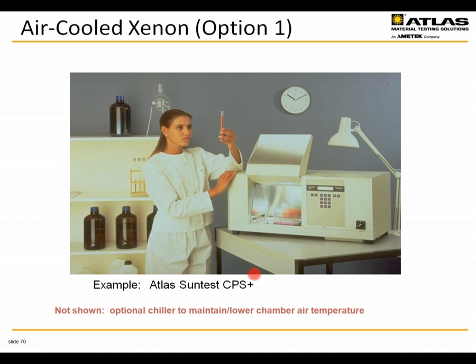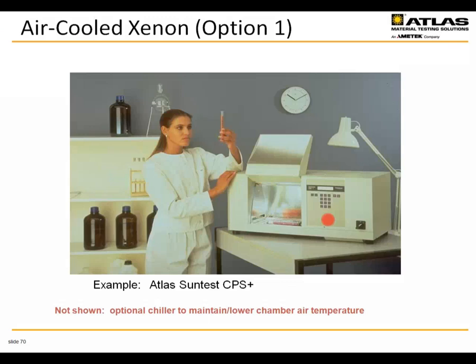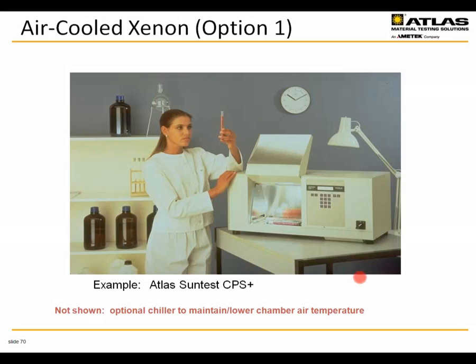An example device is the Atlas SunTest CPS Plus. The light source is located in the ceiling of the device along with appropriate D65 or ID65 filters. Test specimens are placed on a sample tray, and various reflectors and optical systems provide high spatial uniformity over the exposure area. The controls are computer controlled so you can set the light intensity and duration of exposure for unattended operation. There is also an optional chiller attachment for thermally labile samples to maintain a lower test temperature.